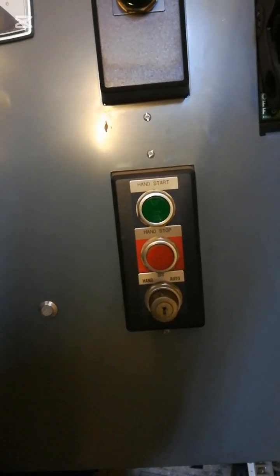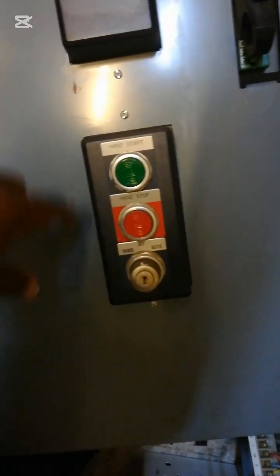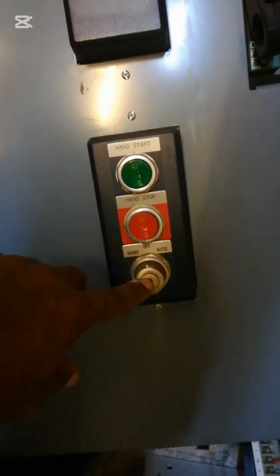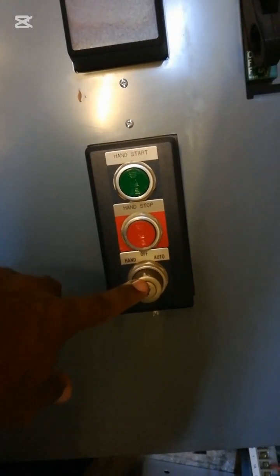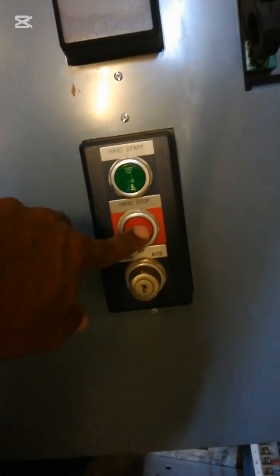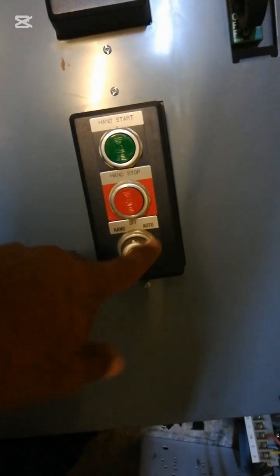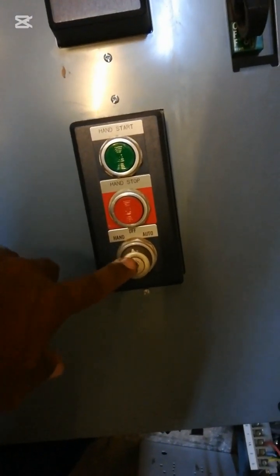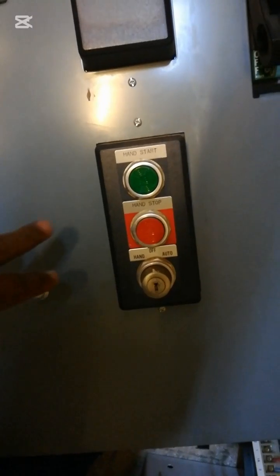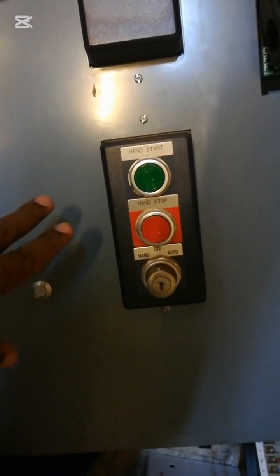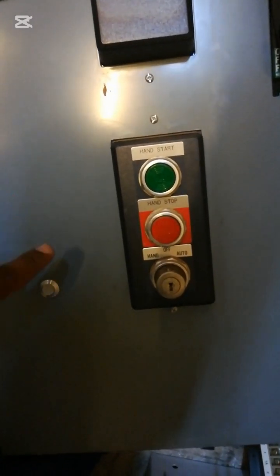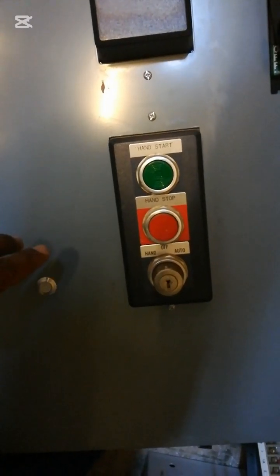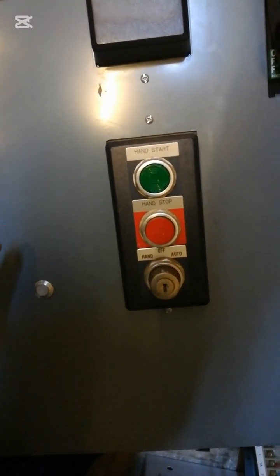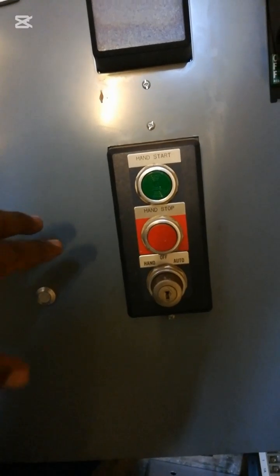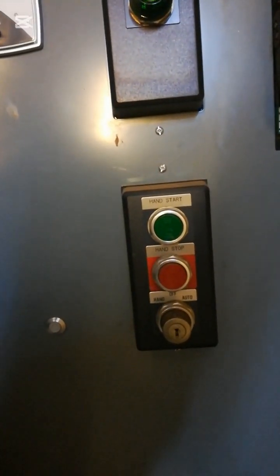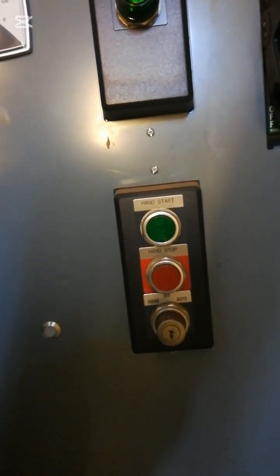The remote out in the field would have a similar setting like this, except the auto switch, the selector switch, it will just have a stop and start. When it is in the auto position, the selector switch will show that it can be started from a remote location by means of a signal, whether a digital signal or an analog signal, which would mean you would have to have a relay in the circuit which would now be able to stop and start it from a remote location.